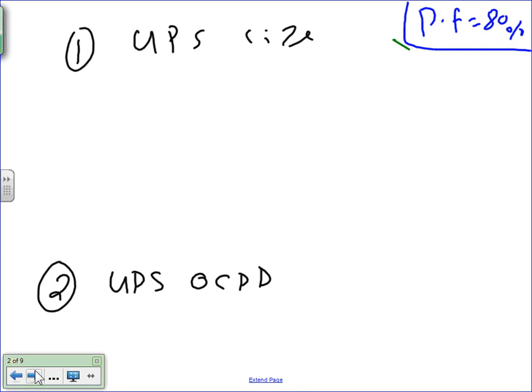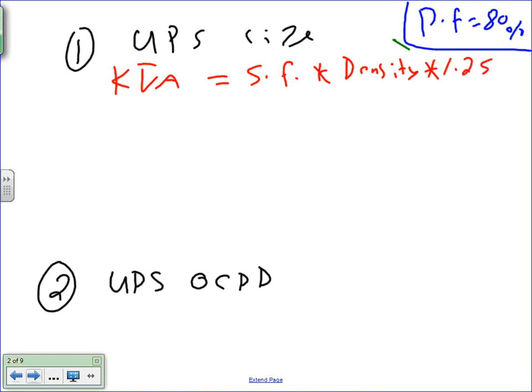Okay, the first thing that we need to do, guys, is that little formula that I gave you. A lot of these are opinion, guys, so there is no code reference to it. Find the kVA for the UPS. I told you this: square foot multiplied by density, multiplied by 1.25. That's for the losses and all this good stuff. And divide by the power factor and by 1,000. If you plug all this good stuff into your formula.